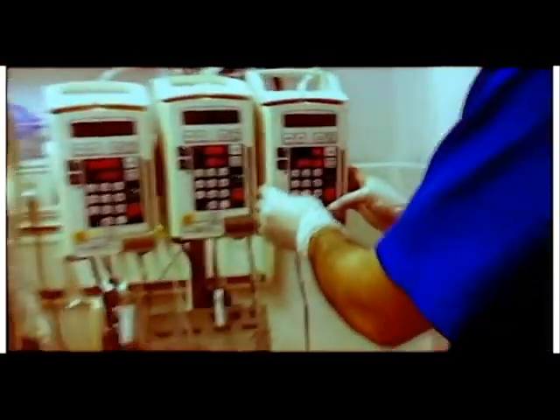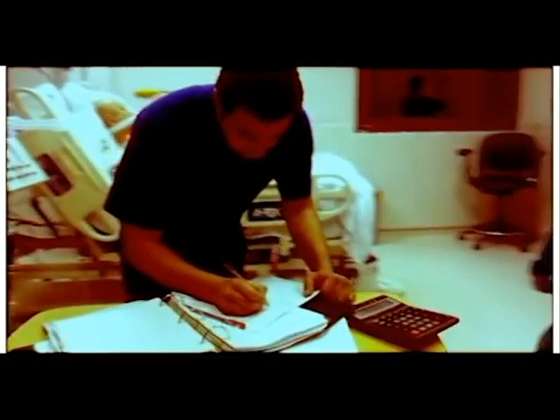The monitor is usually wall mounted. The problem with headwall design is the requirement in an emergency situation to move the bed away from the wall. During an emergency the bed must be relocated to allow access to the patient's airway, which usually involves having to step carefully over various lines and connections in order to reach the head of the bed.